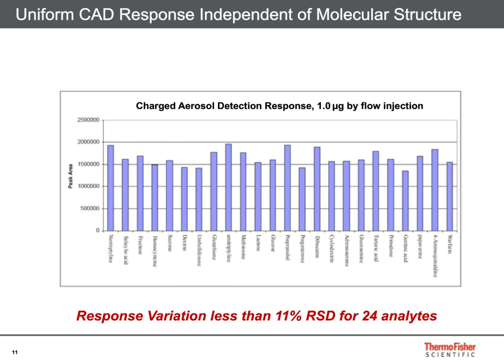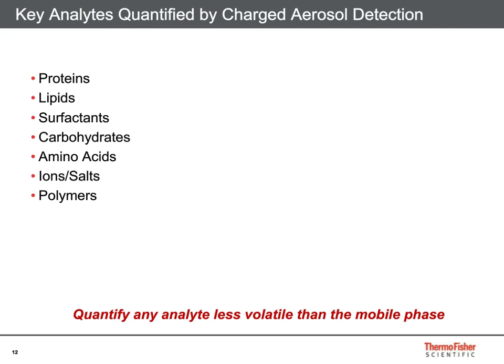Note that this experiment was performed by flow injection analysis to compare detector response independently of other factors. Analytes with vapor pressure greater than about 10⁻³ torr are generally too volatile for charged aerosol detection. Charged aerosol detection provides sensitive, quantitative measurement of many compounds including proteins, lipids, surfactants, simple sugars, complex oligosaccharides, underivatized amino acids, inorganic and organic ions, polymers, and amines. Dr. Bailey will provide example applications for many of these analytes in the second half of today's webinar.